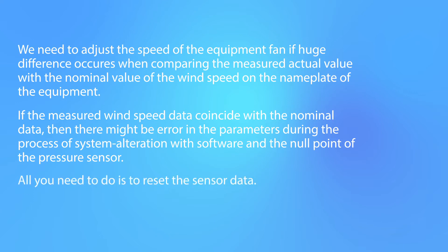If the measured wind speed data coincides with the nominal data, then there might be an error in the parameters during the process of system alteration with software, or an error in the null point of the pressure sensor. All you need to do is reset the sensor data.